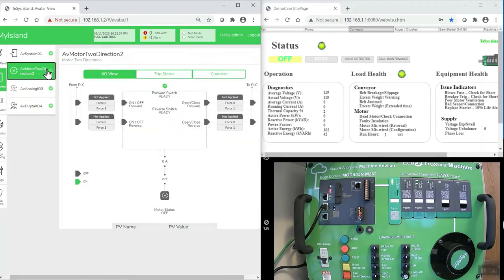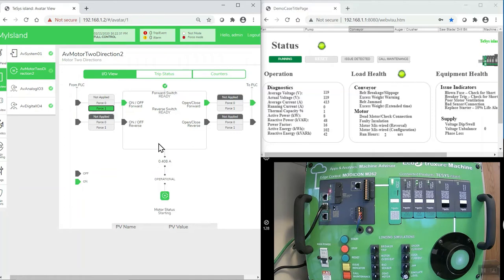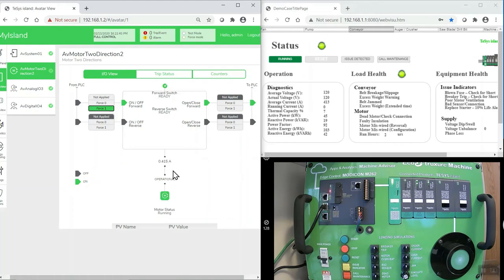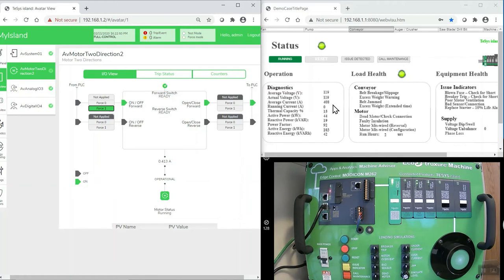I'll be utilizing the forcing functions to turn the motor on. You can see with the motor running, it's spinning in the lower right-hand corner, and you can see the current that it is drawing. You can also see in the web visualization screens that it's drawing about 400 milliamps, and there is no fault at the current time.